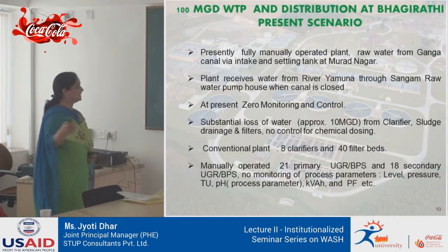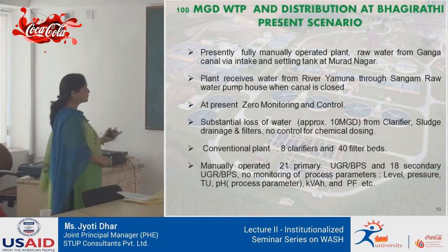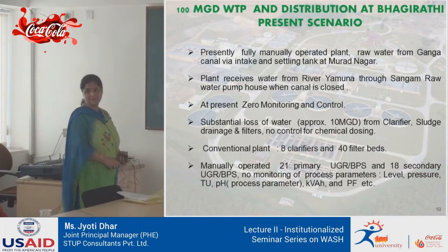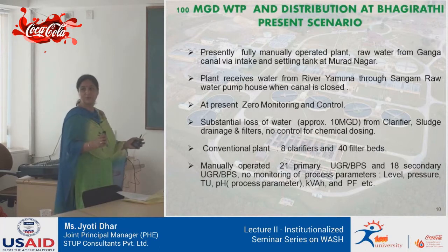Now, I was telling about the Bhagirathi plant which we had commissioned recently. So what was the present scenario of that plant? Let's take a case study of that. Presently, it is a fully manual system. We don't have any controls, we don't have any signals going to the SCADA system, and we don't have any automatic control of the dosing of the pumps.